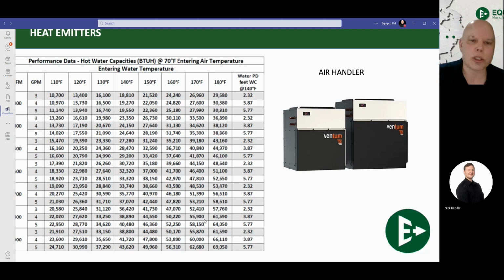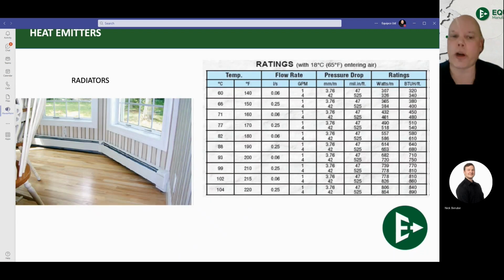But these charts will give you your BTU output, and I can't stress this enough. The only way to know that we've got the unit sized right is by doing that heat loss and knowing exactly how many BTUs we need to put back into that home. So that's where that heat loss really comes from. This is an air handler chart. This is now a chart for Slant/Fin baseboard radiators. It's going to be very similar to pretty much anybody's.